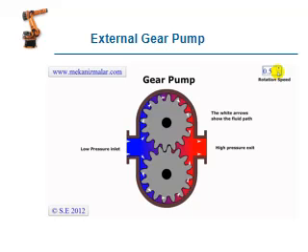So this is an external gear pump. Here there are two gears available. One is interfaced with the motor. If power supply is given to this motor, one gear is rotated clockwise and the other gear is rotated anti-clockwise; the other gear is an idler. If the gear is rotated, a vacuum is created between the gear teeth. So here the blue color shows the oil entering freshly, then the oil pressure is increased, shown in red color. So in between the teeth the pressure is increased.